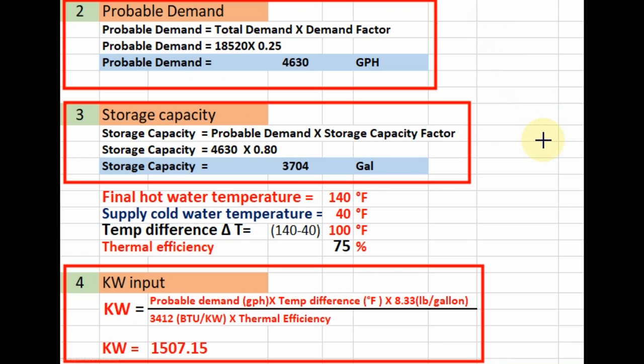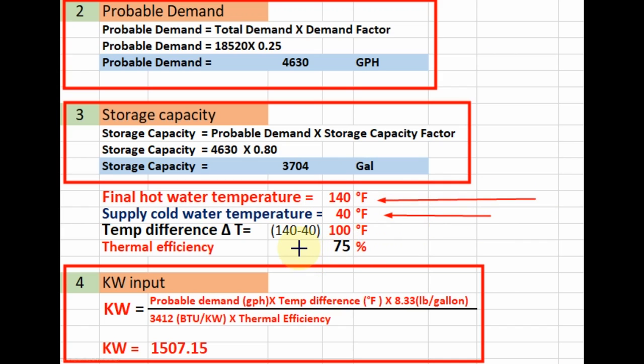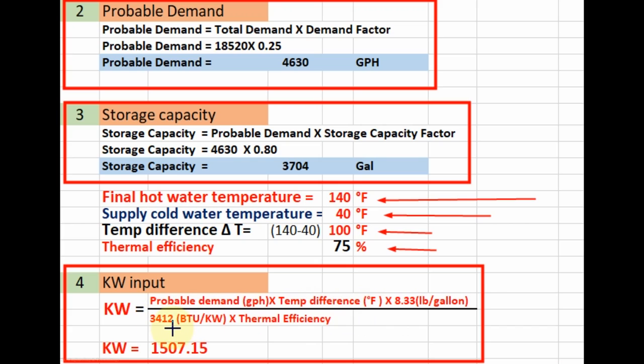Now we will calculate the power required in kW for our water heater. We assume the hot water final temperature is 140°F. Assuming cold water temperature is 40°F, the temperature difference is 100°F. Assuming thermal efficiency of 75%, the formula is: kW = probable demand × temperature difference in °F × 8.33 divided by 3,412 × thermal efficiency. Applying these values, the power required for our water heater is 1,507.15 kW.